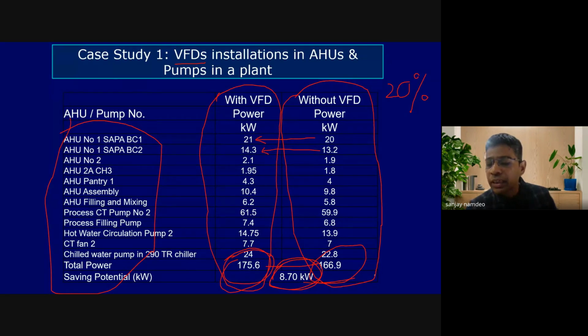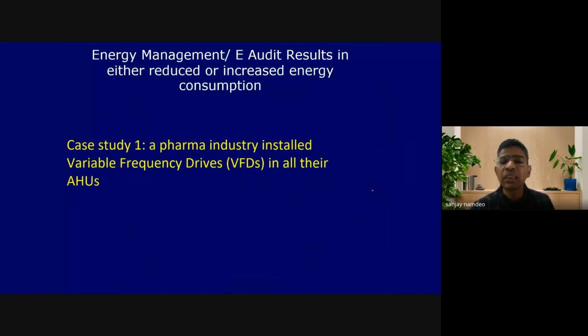And if you calculate the monetary value of this 8.7 kilowatt, assuming 320 days per year of operation, 24 hours per day, and a power cost of around 7 rupees, it would be significant, around 7 to 10 lakh rupees of loss. So it's a double loss for the industry. One is the capex they spent on this project, and the other is the recurring power cost, which has gone up. This is happening in many of the cases.